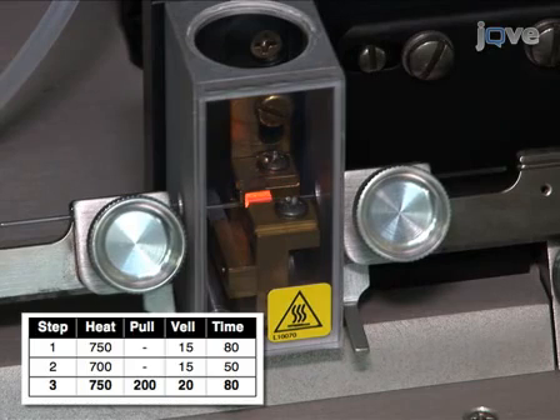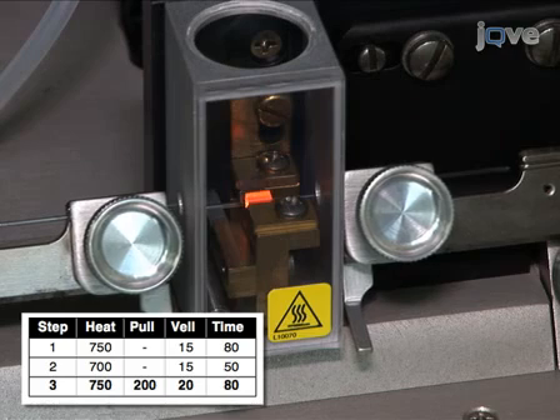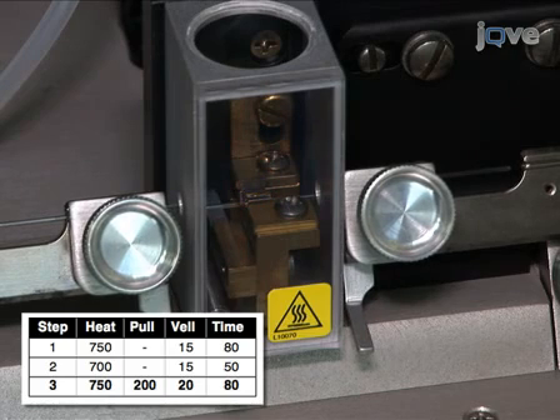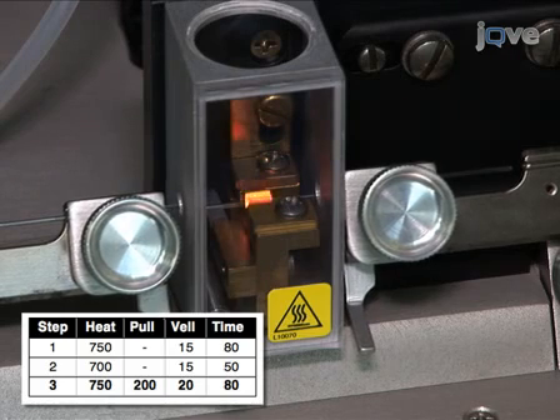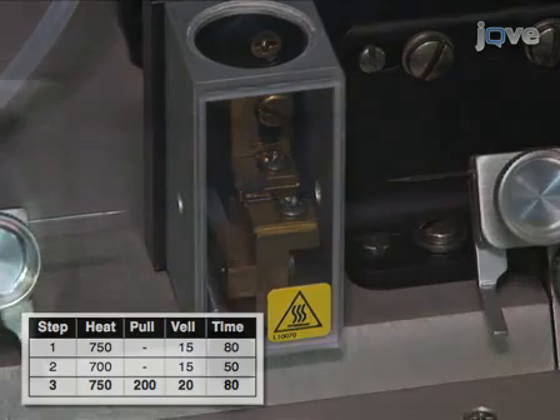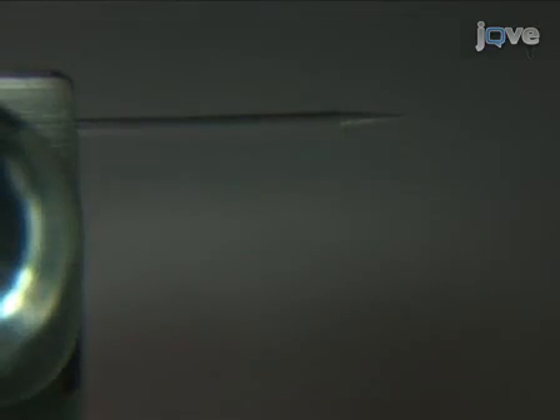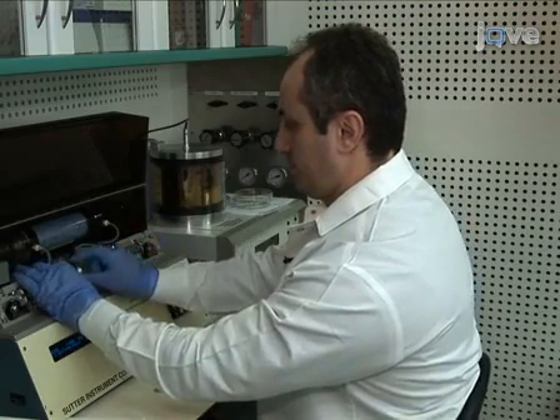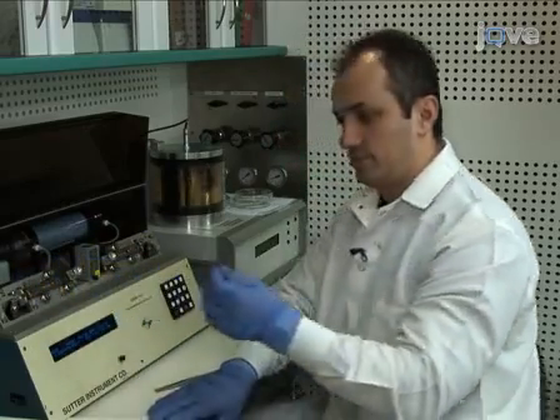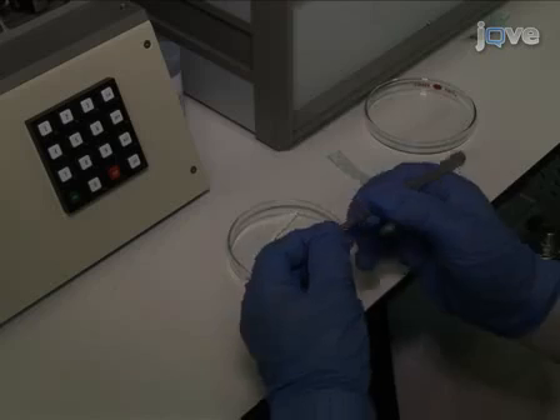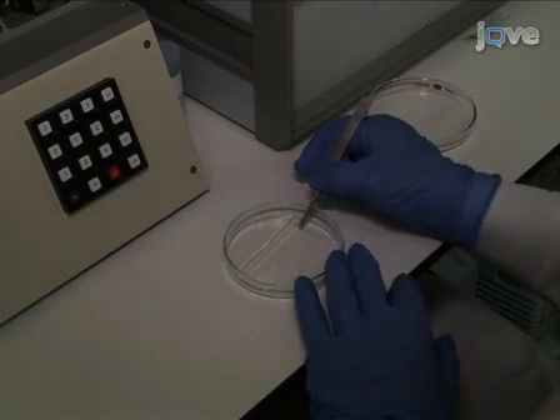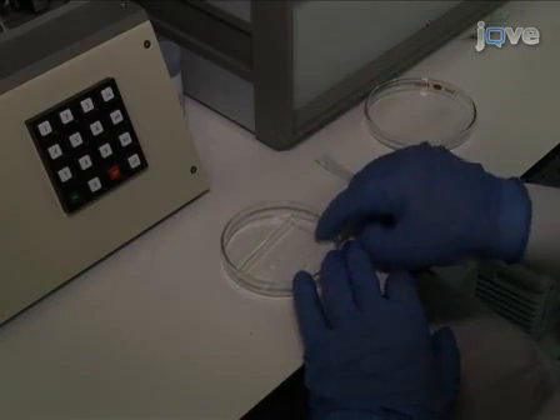However, remember that the process of programming the puller is one of trial and error until an acceptable tip shape is obtained. Every capillary pulled gives rise to 2 final shaped capillaries. Remove the pulled capillaries from the instrument and inspect the tips, discarding any that are deformed or broken. Use blunt positioning tweezers to place the capillaries in the petri dish.